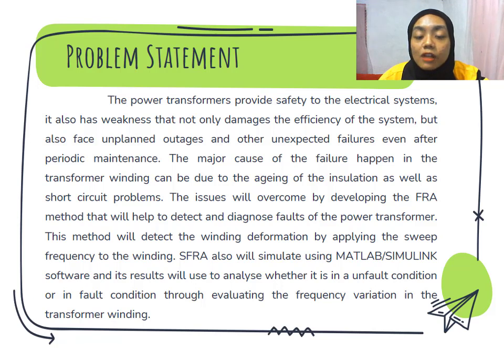The issues will be overcome by developing the FRA method that will help to detect and diagnose the faults of power transformers. This method will detect the winding deformation by applying the sweep frequency response to the winding. Sweep frequency response analysis will also be simulated using MATLAB or SIMULINK software, and its result will be used to analyze whether it is in unfault condition or fault condition by evaluating the frequency variation in the transformer winding.